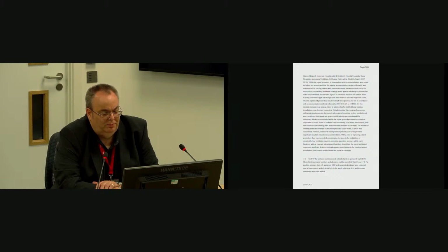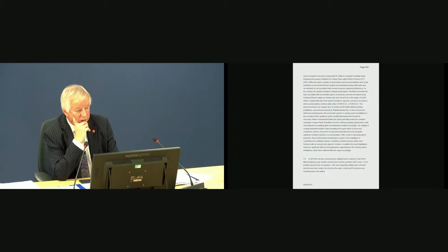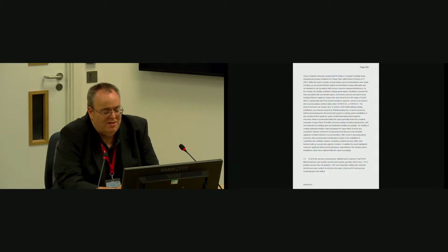Thank you. I might just ask you about that. Have you seen wards for that type of patient cohort with higher standards than that? You can increase both air change rate and pressure differentials. Bigger isn't necessarily better, because it can introduce problems operationally, getting doors to close and stay closed. You can also get back eddies when doors are open, and that can introduce problems. If it is airlocked and at a general 10 pascal positive pressure to surrounding areas, that is appropriate.